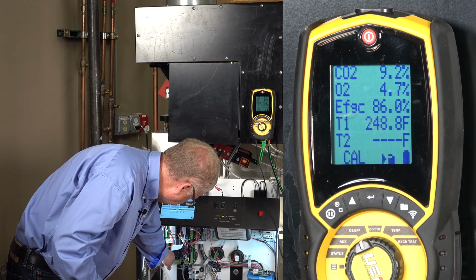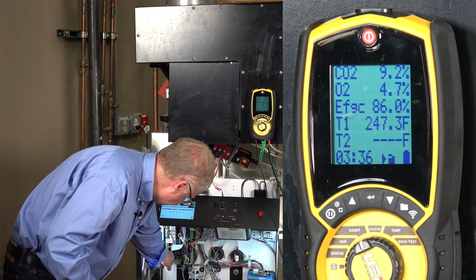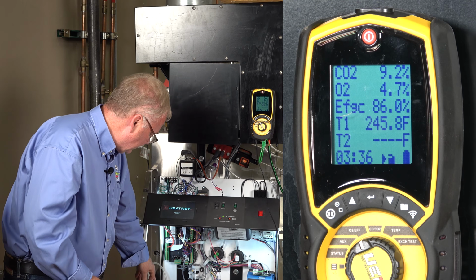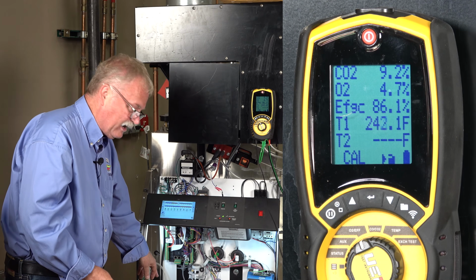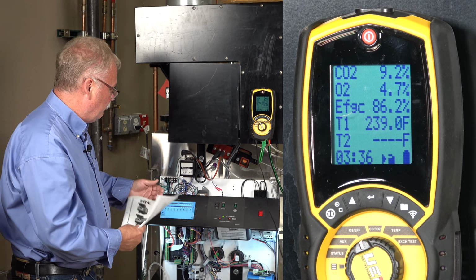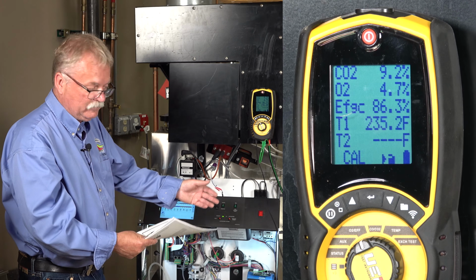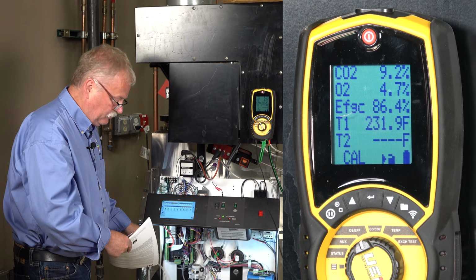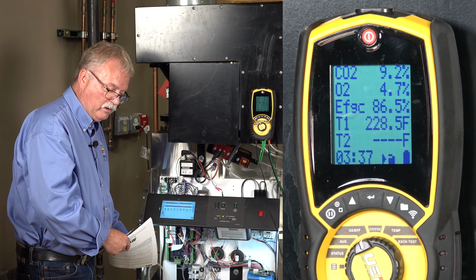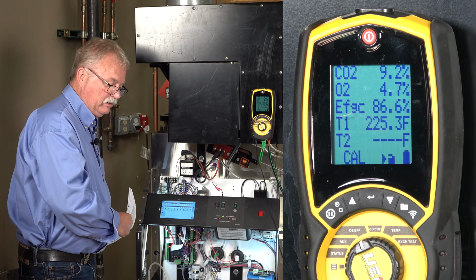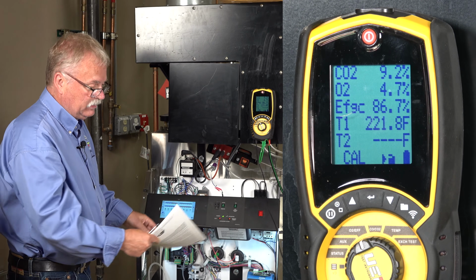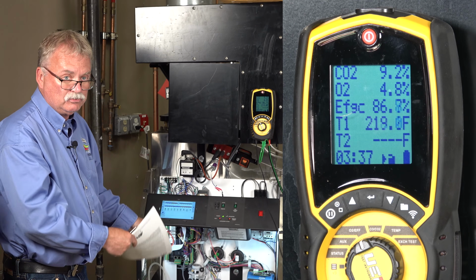I'm going to shut off the calibration mode, which is down here. I'm just reviewing my gas. It only dropped to 6.2 on high fire. If you have multiple boilers in the system, it's very important that you have your gas meter on one of them, or a common point is the best, where you can turn on all three boilers and make sure you don't drop below your minimum.